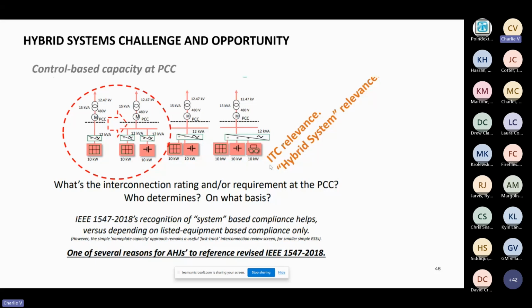Now here's one of the devils in the detail. I couldn't tell from the ruling whether that export capability limit, using controls or a system-level project controller, also applies to the power rating at the interface. Because one issue that keeps coming up, and this isn't just me — this is an IEEE slide — is especially for retrofits where a solar system adds energy storage.